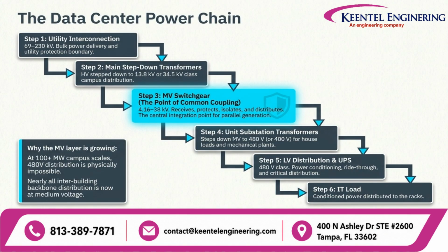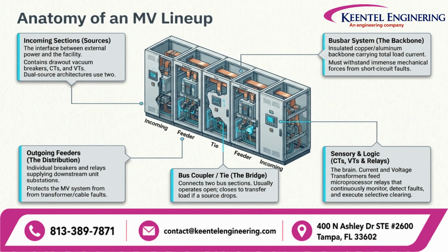The data center power chain moves through several stages, from utility interconnection down to IT load. Step 3, the medium voltage switchgear, serves as the central point of coupling and integration for parallel generation, making it a critical focus area. Understanding the anatomy of an MV lineup is essential. It includes incoming source sections, a robust busbar system, outgoing feeders for distribution, and the sensory and logic components, like relays, that function as the brain of the system.